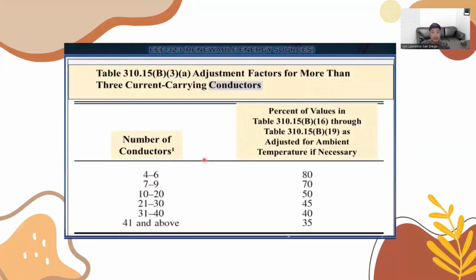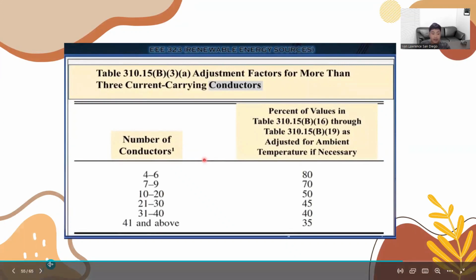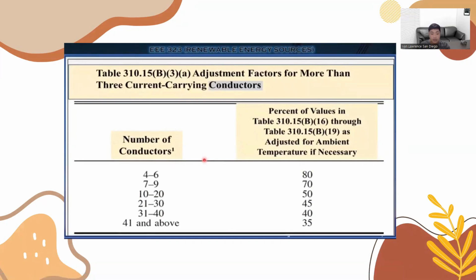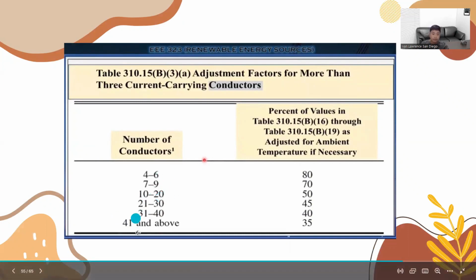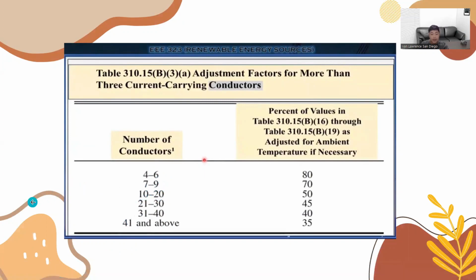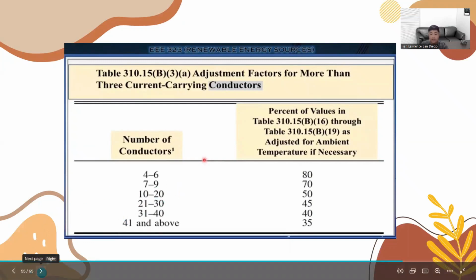Ito naman yung example din ng table 310.15B3A, adjustment factors for more than 3 current carrying conductors. Nakita natin dito yung number of conductors. Una dito is yung 4 to 6 na merong 80% of values ng table 310.15b16 through table 310.15b19 as adjusted for ambient temperature if necessary. At meron din tayong 7 to 9 na meron din namang 70, and yung 10 to 20 na karoon ng value na 50. So, screenshot na lang din.